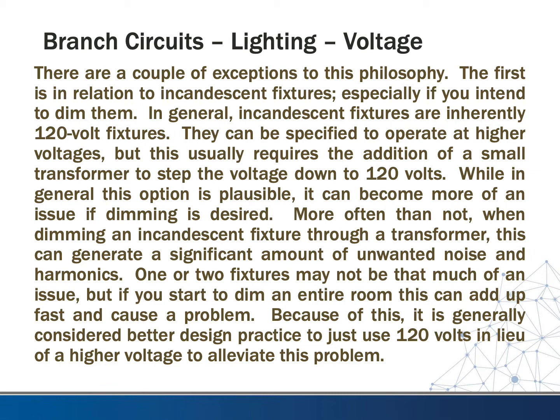There are exceptions to this philosophy. The first relates to incandescent fixtures, especially if dimming is intended. Incandescent fixtures are inherently 120-volt fixtures; operating at higher voltages requires a small step-down transformer. When dimming incandescent fixtures through a transformer, this can generate significant unwanted noise and harmonics — one or two fixtures may be manageable, but dimming an entire room can cause a real problem. Because of this, it is generally considered better design practice to use 120 volts for incandescent dimming applications.